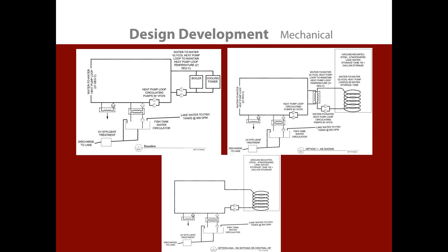So then we say, well, what if we have a central heat pump that has a loop in the big water storage tank? Then we can have this heat pump running, and we don't have an inefficient boiler running all year, so we're saving a good amount of energy. But then we look at this central heat pump that tempers this loop, and we think, well, why do we need that? Why do we bother tempering this loop? So we take away that central heat pump, and then all the individual heat pumps take care of the load.